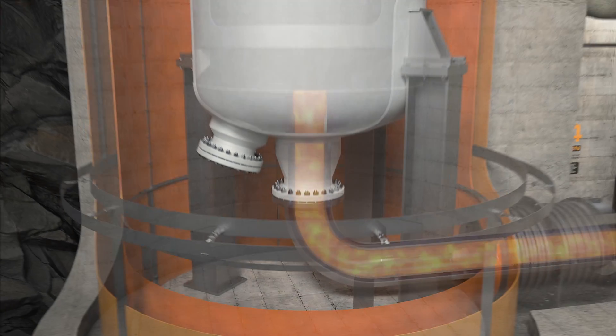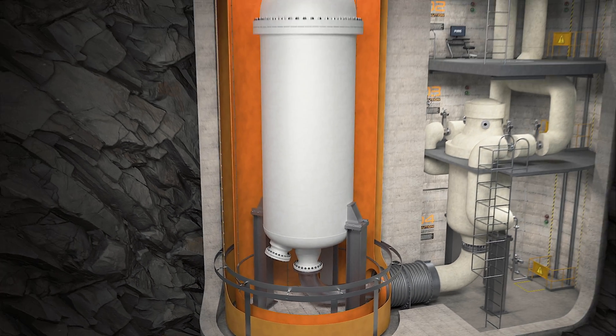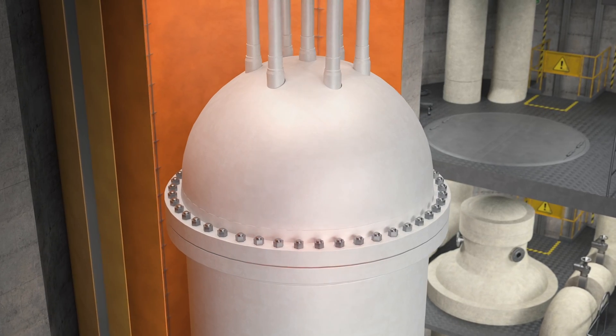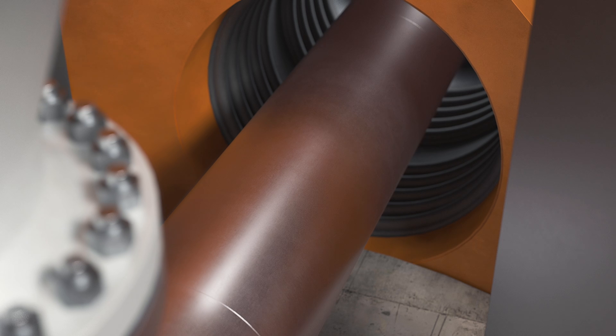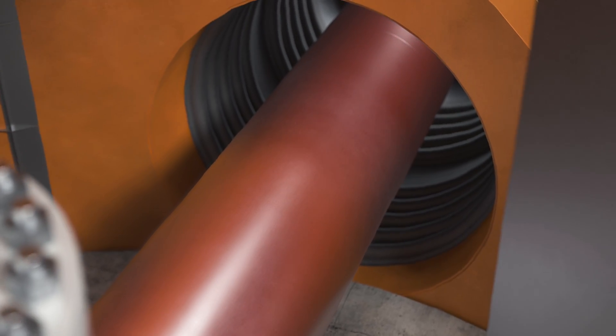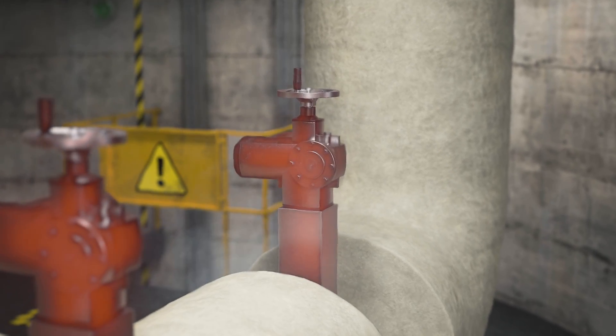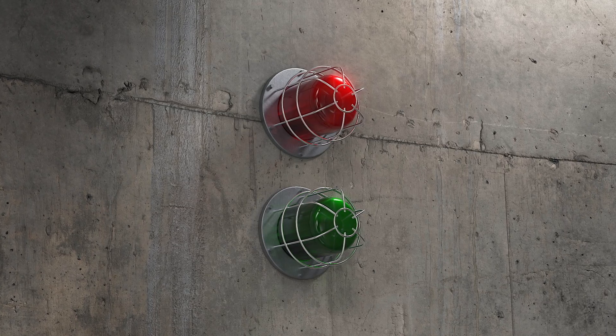Now, the problem with nuclear fuel is that it continues to generate heat even after the reactor is powered down. It will continue to generate roughly 10% of the original heat for hours and days to come. And if it is not cooled, that heat will pile up. The challenge with nuclear has always been to ensure the reactor does not damage itself when cooling is lost.